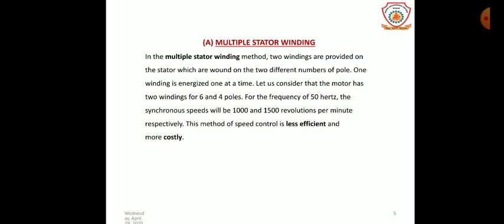The limitations of this method are: first, it can only be applied to squirrel cage motors; second, smooth speed control is not possible — only step changes in speed are possible; third, two different stator windings are required, which increases the cost of the motor and is complicated from a design point of view. Overall, this method of speed control is less efficient and more costly.